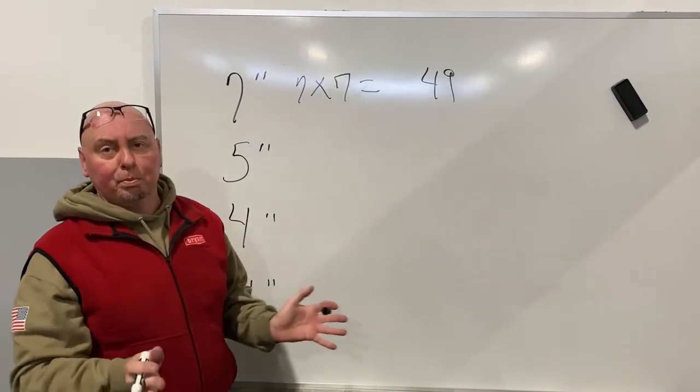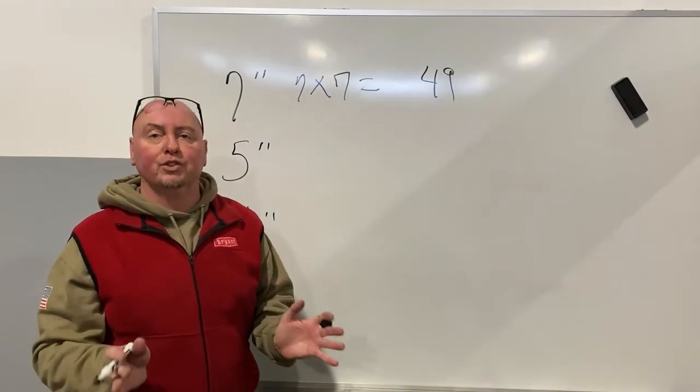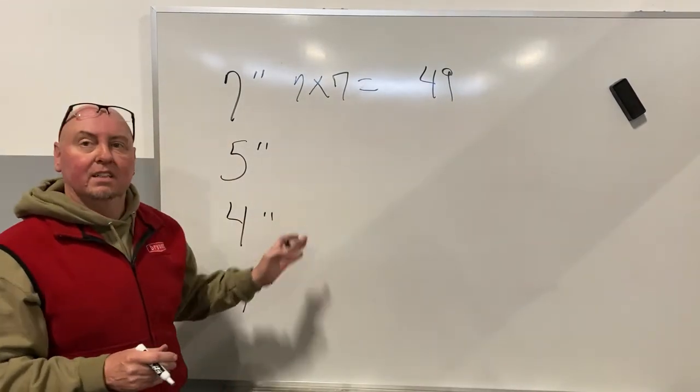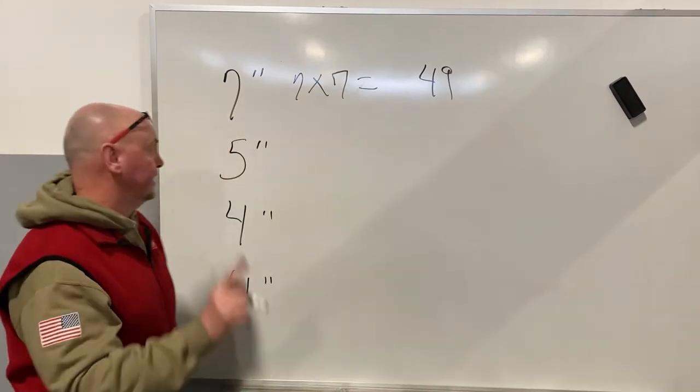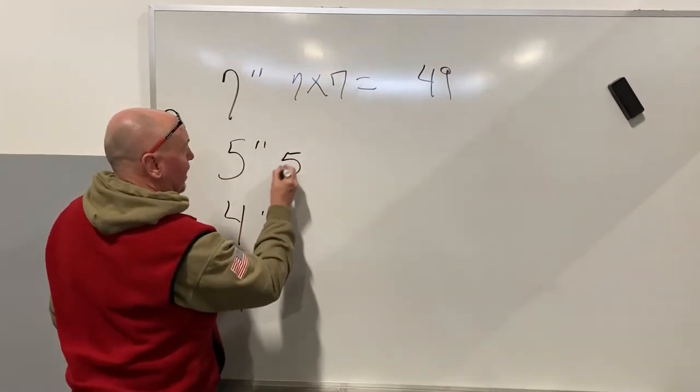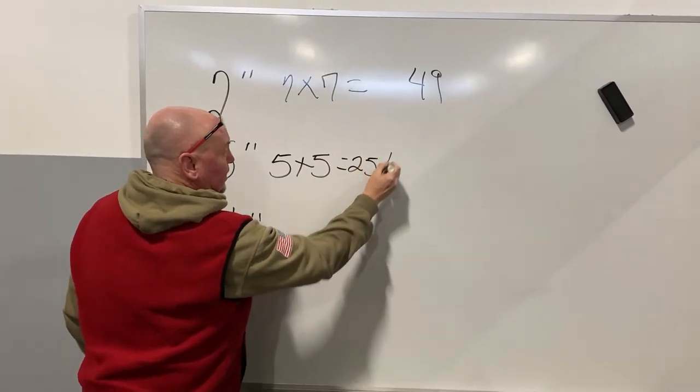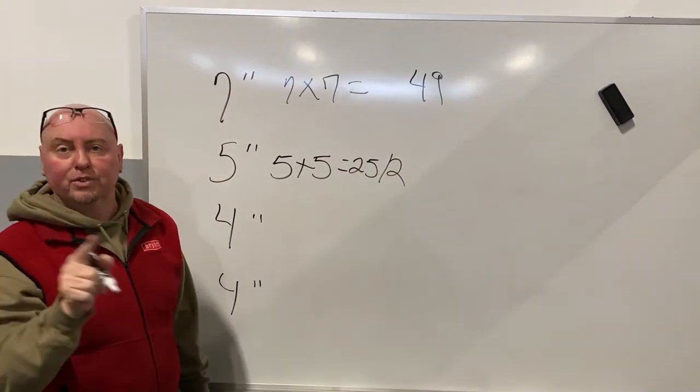You need 100% of that appliance, 100% of the largest appliance. Now here's the 50% rule. The other ones, you take 50%, same formula, 5 times 5 is 25, but divide by 2. I need 50% of that.